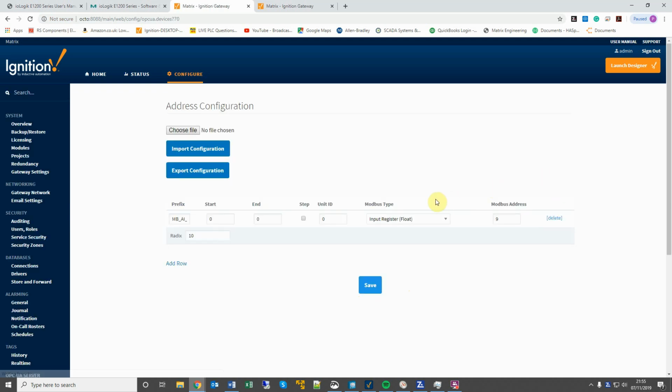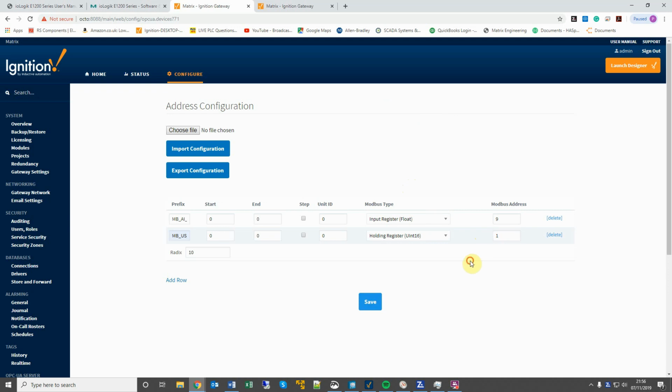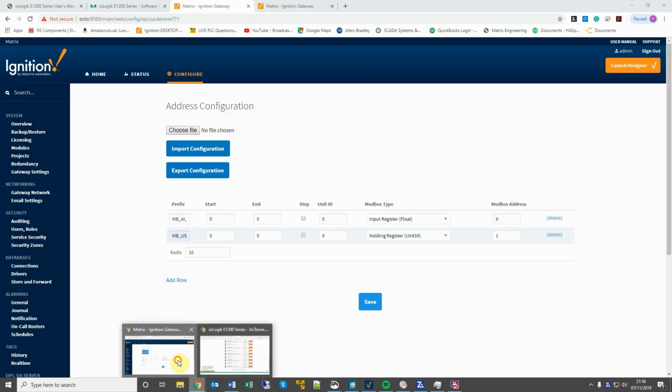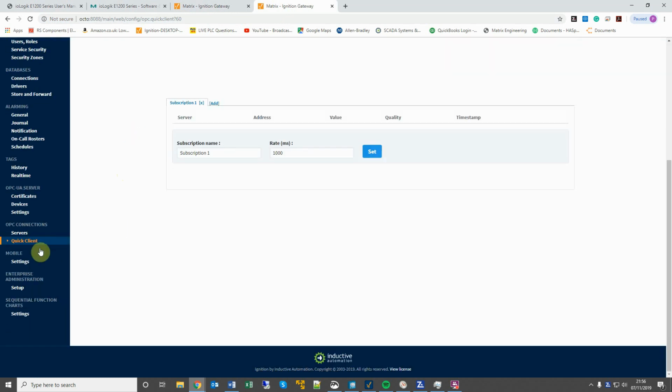I'm also then going to add another row, and that's going to be for US for unscaled. Again, starting at 0, 0, creating one tag, and that is going to be an holding register UINT16 starting at 1. Just jumping back into the Moxa software, starting at 1 for the raw value and it's 1 word, starting at 9 for the scaled float value, which is 2 words.